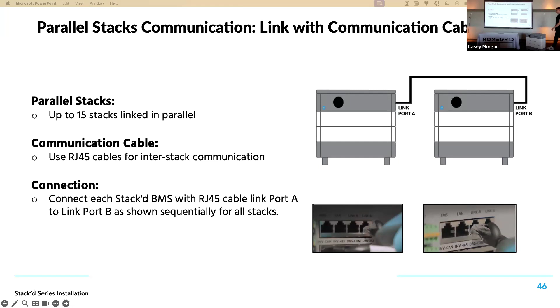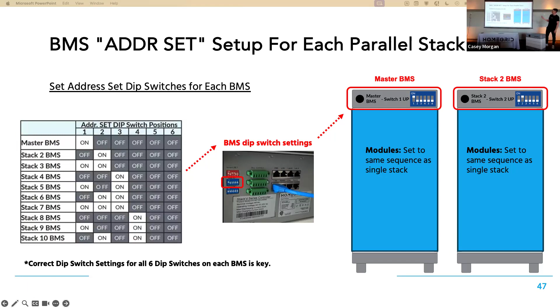We're going to set the address dip switches of the BMSs according to their stack position in parallel. You know how we set the modules to their position in the stack? Now we set the dip switches the same way: this is number 1, this is number 2, this is number 3, this is number 4. You do that on the blue dip switches, binary as well, same code as the modules. Once that's done, go to the next slide.